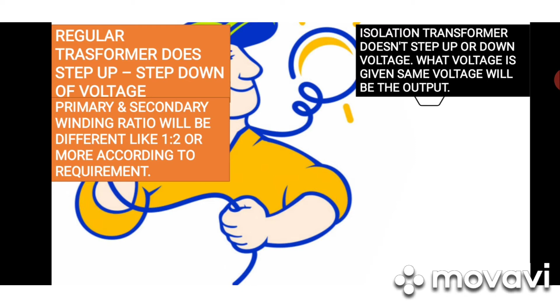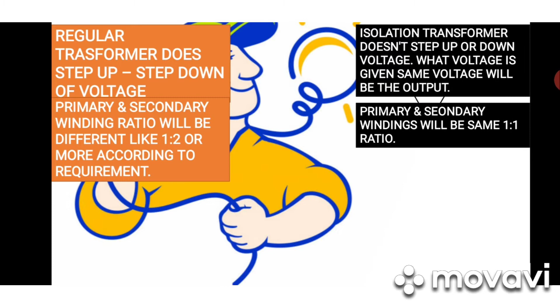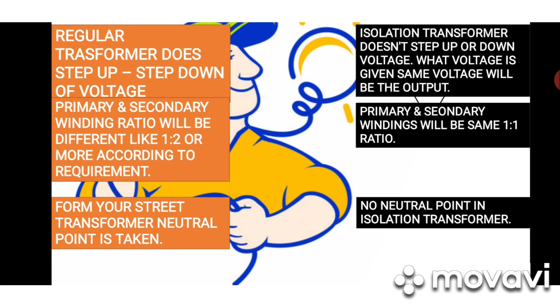In a regular transformer, the winding ratio will be like 1:2 or 1:4, depending on the design and requirement. But in an isolation transformer, there will be only a 1:1 ratio winding, so whatever input we give, the same output comes out. In your normal street transformer, there will be a neutral point taken out as a tapping, since it's a star-wound transformer. But in an isolation transformer, there is no neutral. So isolation transformers are used in electronic circuits, etc., for safety purposes.